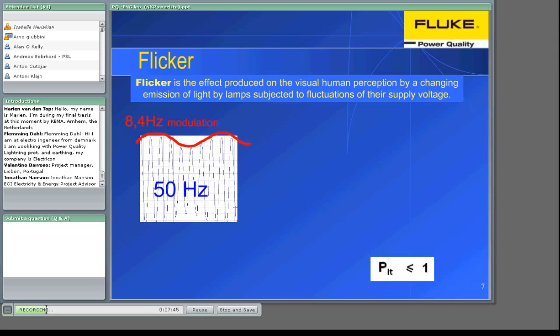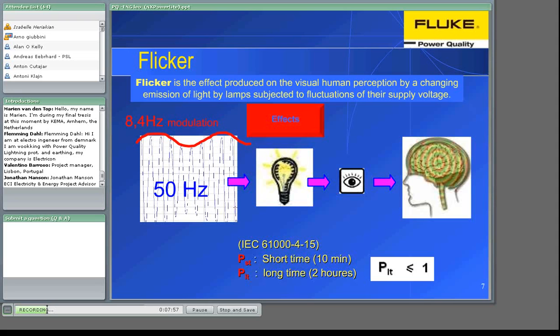The flicker effect. We say that it is a voltage variation, but a specific one, having the characteristic of being visible and a nuisance. Tests in laboratory have demonstrated that the human eye is very sensitive to voltage RMS variation, in other words, 50 Hz modulation, whose frequency is around 8 Hz. The flicker itself has no unit such as volts and amps. It is defined by artificial units called PST and PLT, short time and long time. The PLT unit, which is valid for the standard and whose unit value is 1, is calculated after 12 PST.